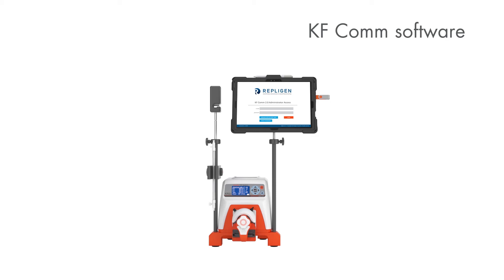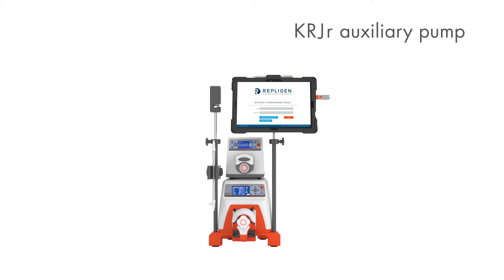The KF Comm software provides preset automated control modes and constant feed concentration modes, and collects real-time data such as pressures, flows, and flux. The KR2i can support up to two auxiliary pumps that control permeate flow rates, ensuring controlled and scalable runs.